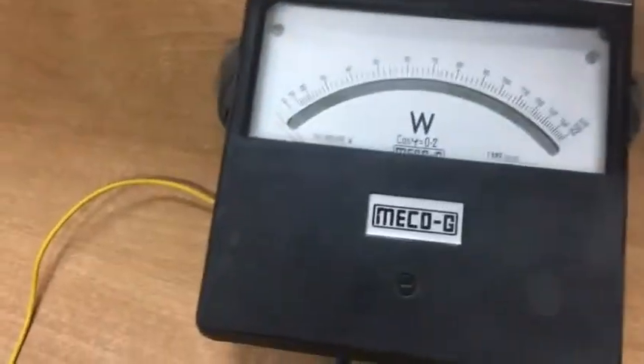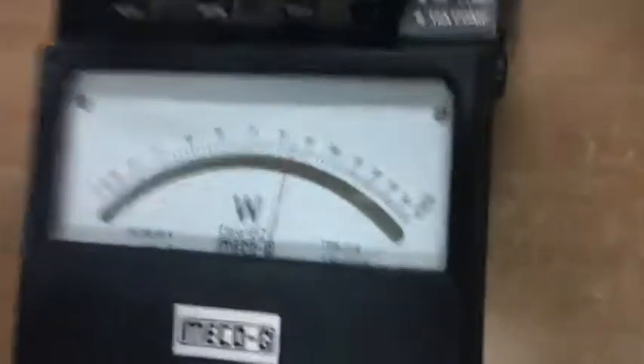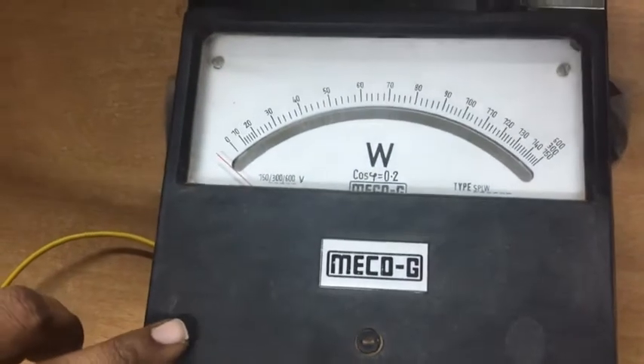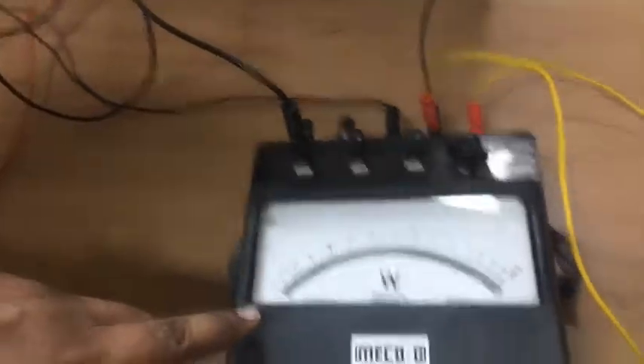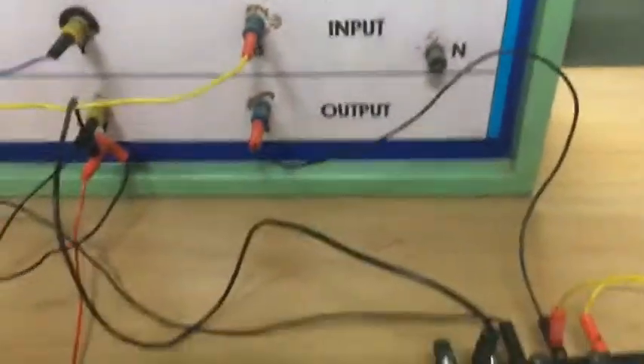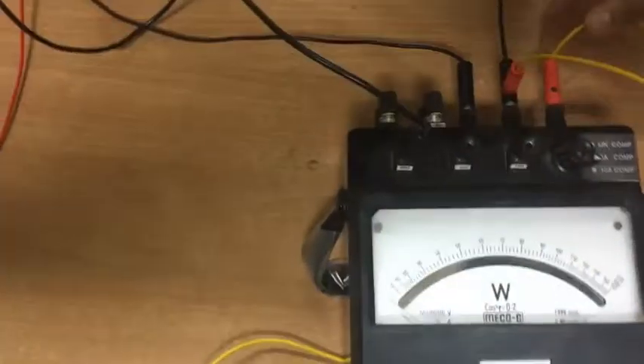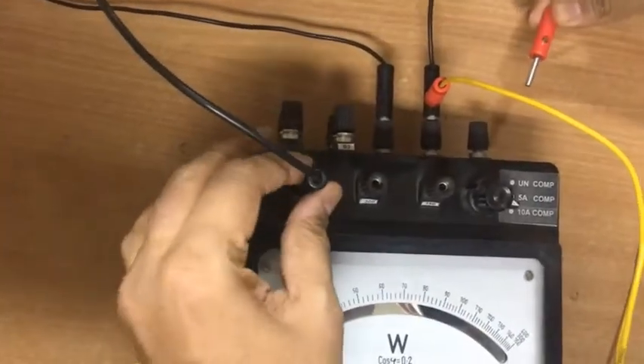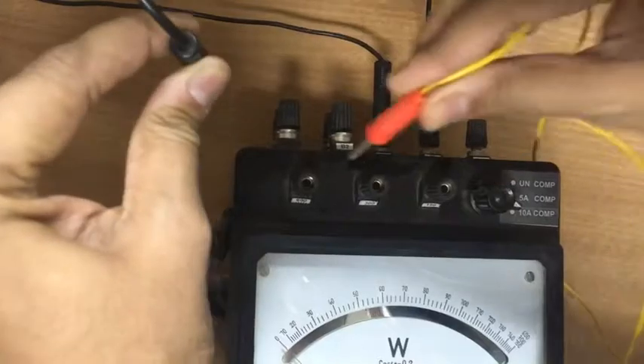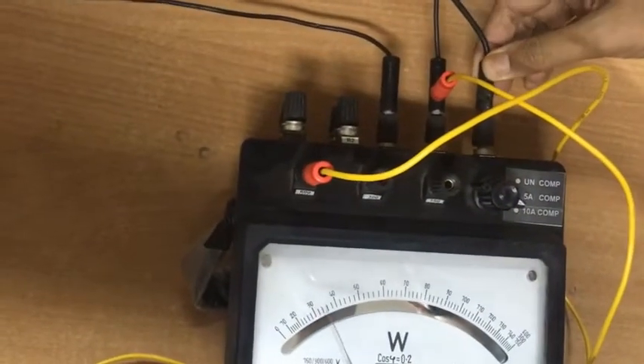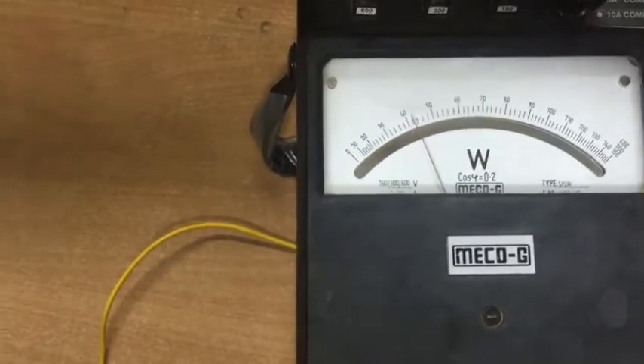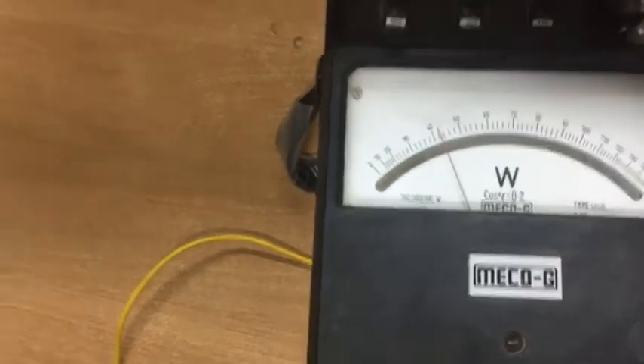Once 450 volts has been applied, check both the wattmeters. One wattmeter shows a positive value and the other wattmeter will be showing a negative value. For the wattmeter which is showing a negative value, please interchange the C and V terminals. And whatever value it is showing, note down that value as a negative value.